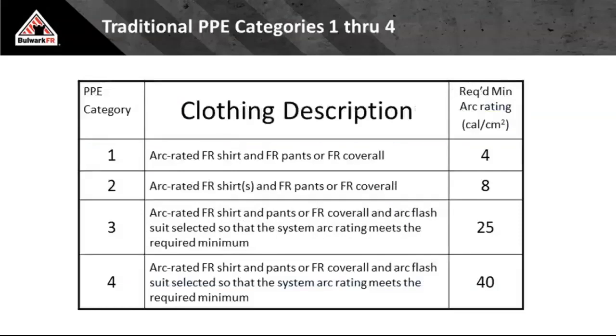We used to have hazard risk category up here on the top left. Now that's PPE category. All the ARC ratings and everything stayed the same. So a Cat 1, Cat 2, Cat 3, Cat 4. That's going to translate to your label that goes on that box if you're using the CAT method.